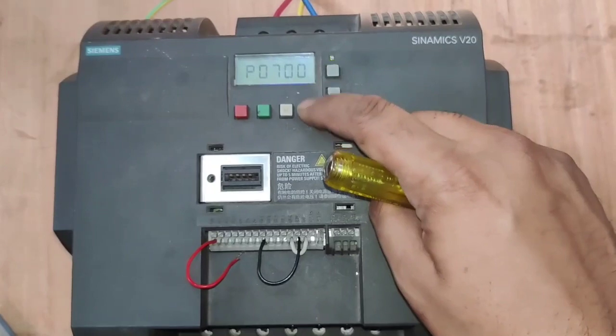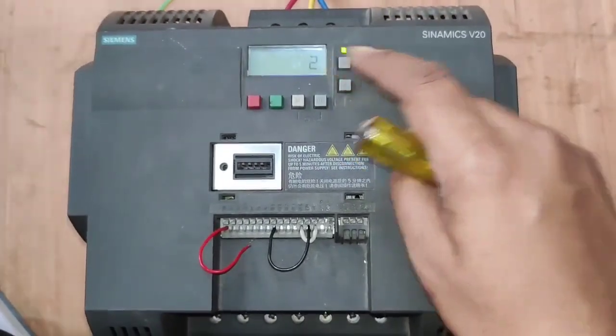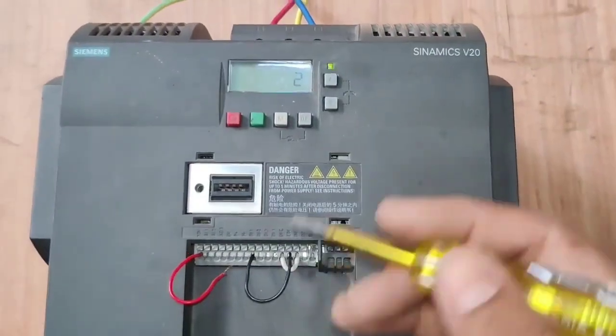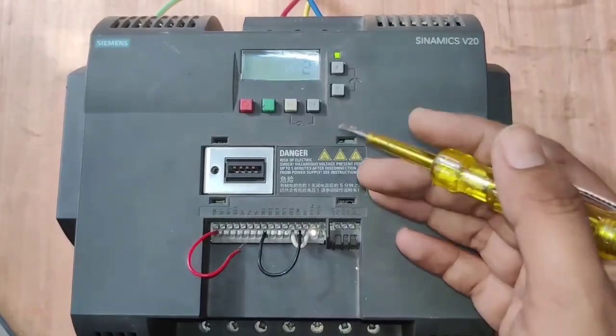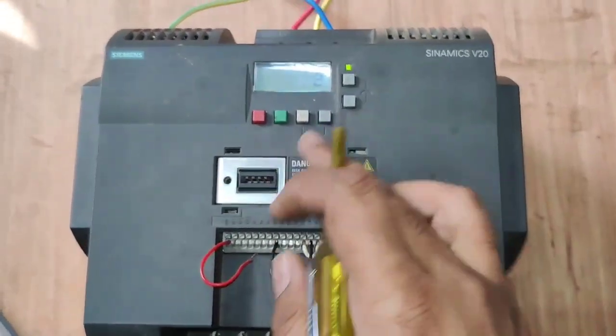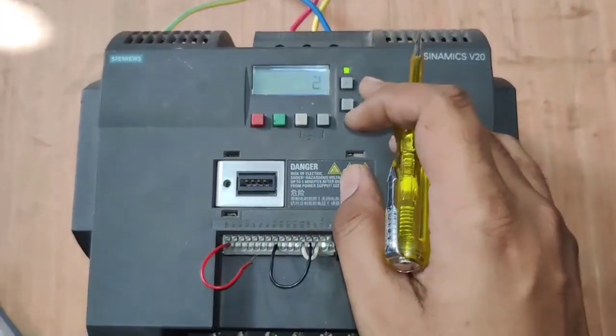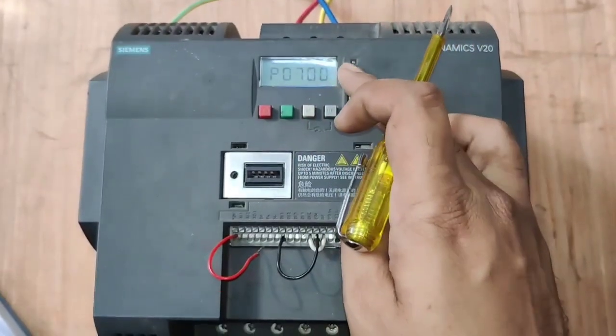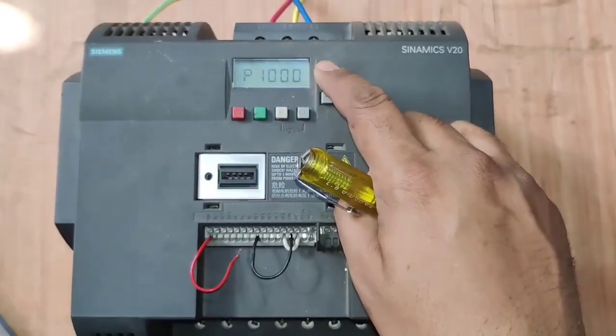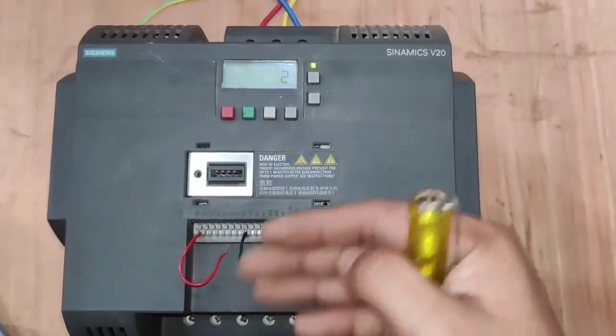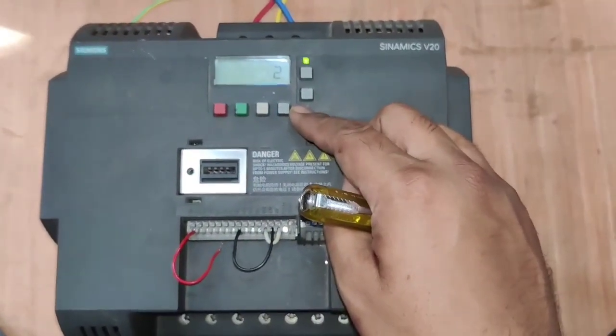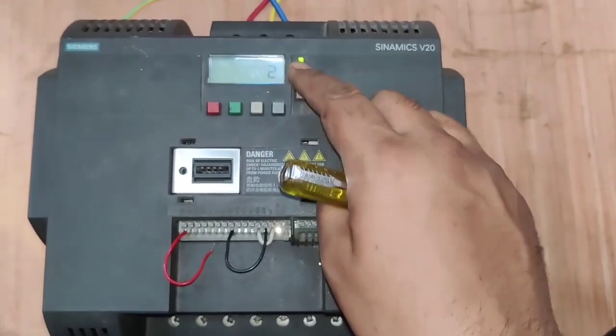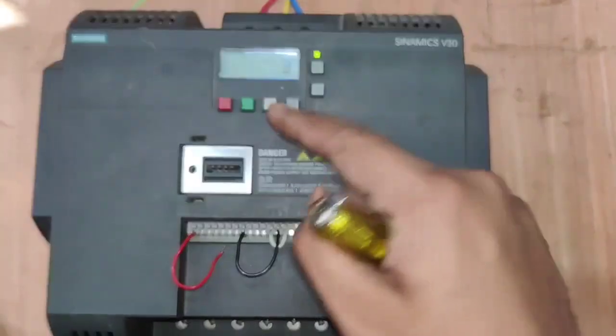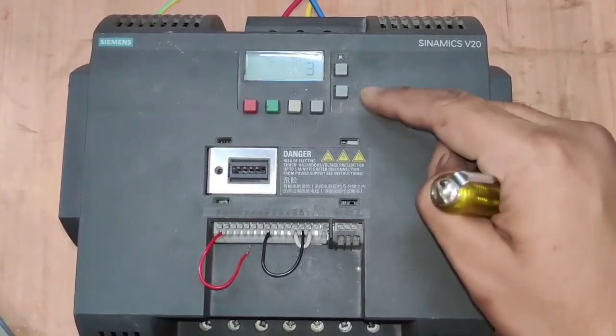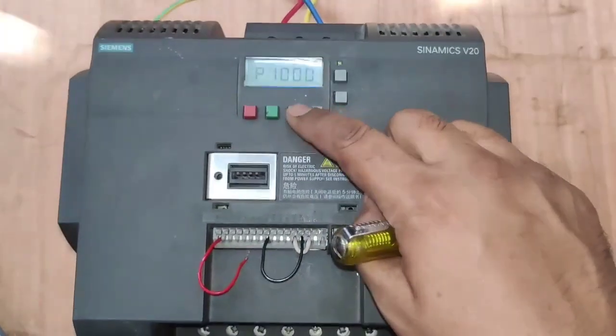You just enter them. Next parameter P700, selection of command source, where you want to start and stop your drive. If you want to start and stop the drive with a push button, you just need to set 2. And if you want to start and stop your motor with the drive keypad, just set 1. For now we set 2 because we want to start and stop the motor with a push button. Next parameter is P1000, which is for selection of frequency setpoint. In this parameter we set 2 if you want to control your motor speed with a potentiometer, because of analog input. And if you want to run your motor at a fixed frequency, you set 3. For now we set 2 because we want to control our motor speed with a potentiometer.